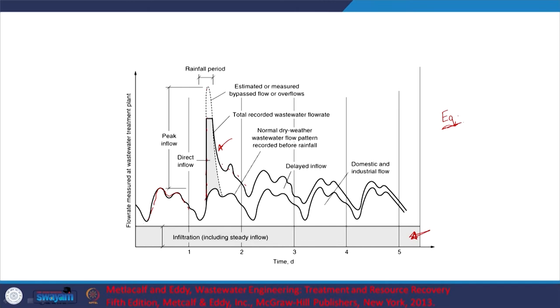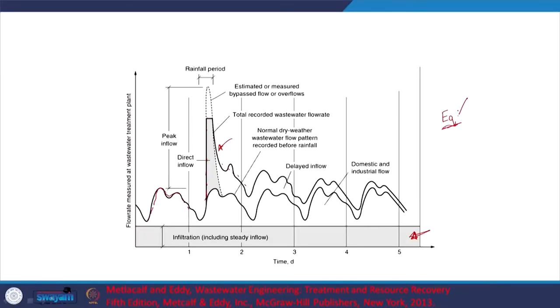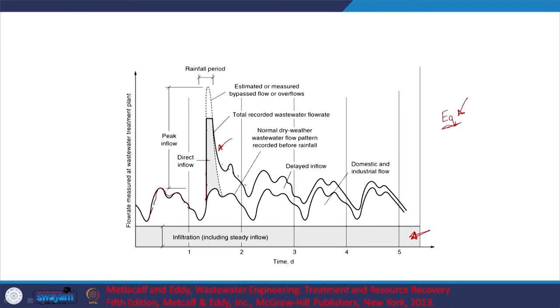An equalization tank helps avoid shock loads. Additionally, if you do not have accurate flow measurement devices or the concentration of the compound you are targeting varies, you will unnecessarily underdose or overdose. To rule out these aspects and have a more effective treatment plant, an equalization tank can be built. In India, sewage treatment plants generally do not go for equalization tanks, though many industrial wastewater treatment plants certainly do.